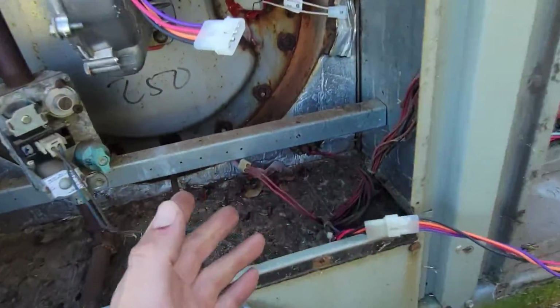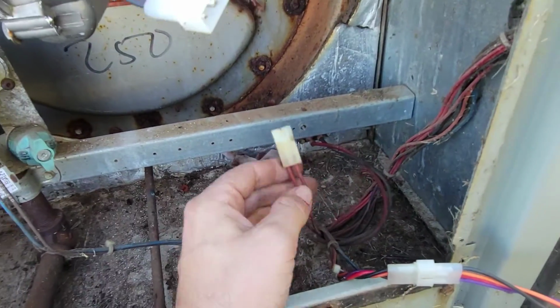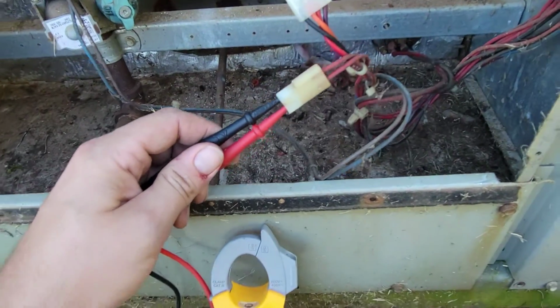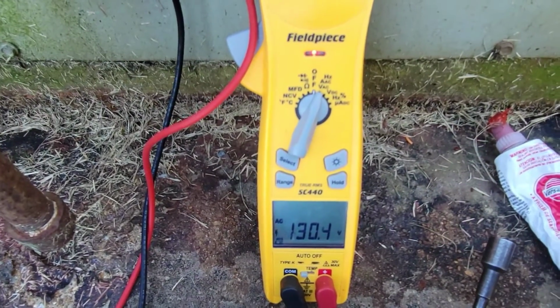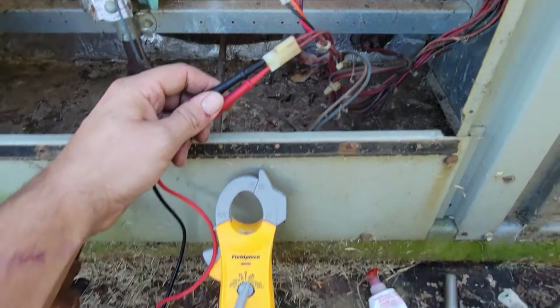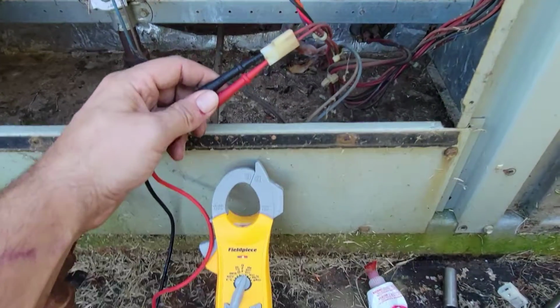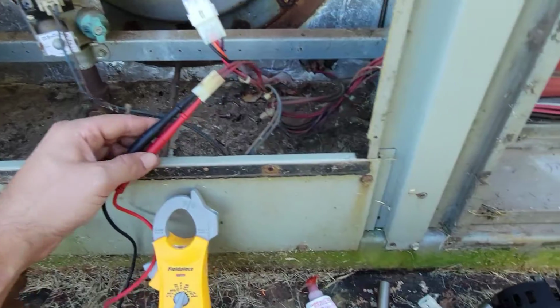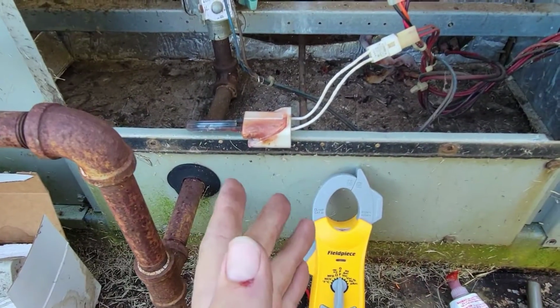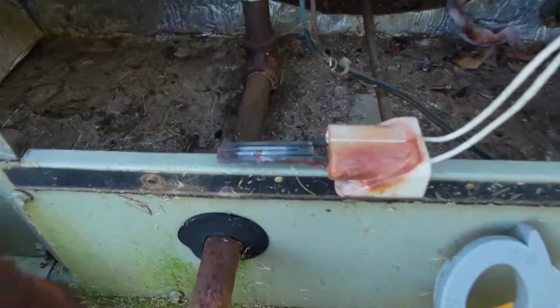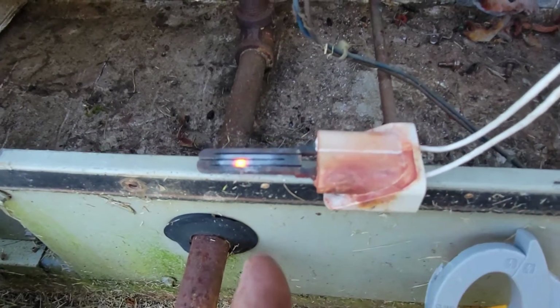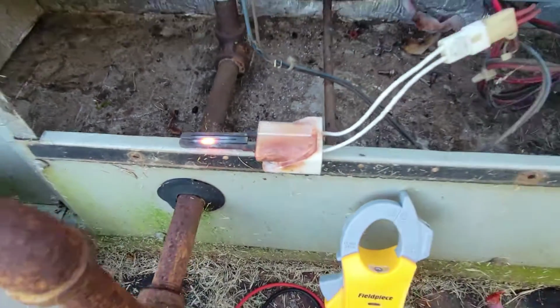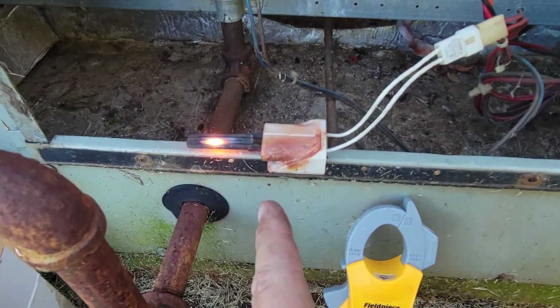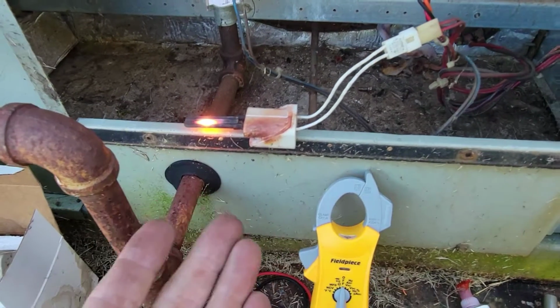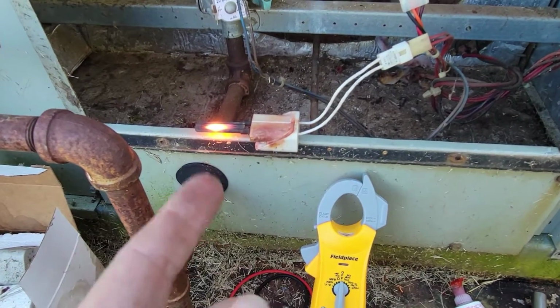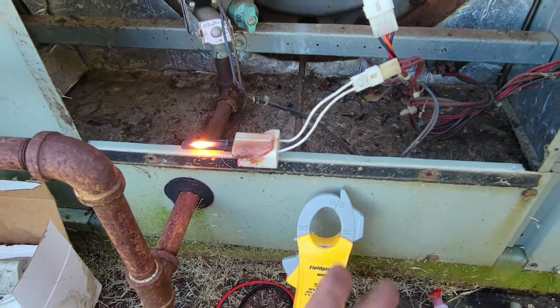All right, let's take a look at the hot surface igniter. The voltage coming from our board should be 120. We're checking the plug to the hot surface igniter. Got 130 volts. That's exactly what we need. I'm going to show you the old hot surface igniter and what it looks like when voltage is applied to a bad hot surface igniter. So this is the bad hot surface igniter. We've got it plugged up, and you can see it's got a little glow, but it's got a crack. See where that crack is? Now let me take this apart and show you how I know this is bad. You can see it's not really glowing because there's a crack in it.